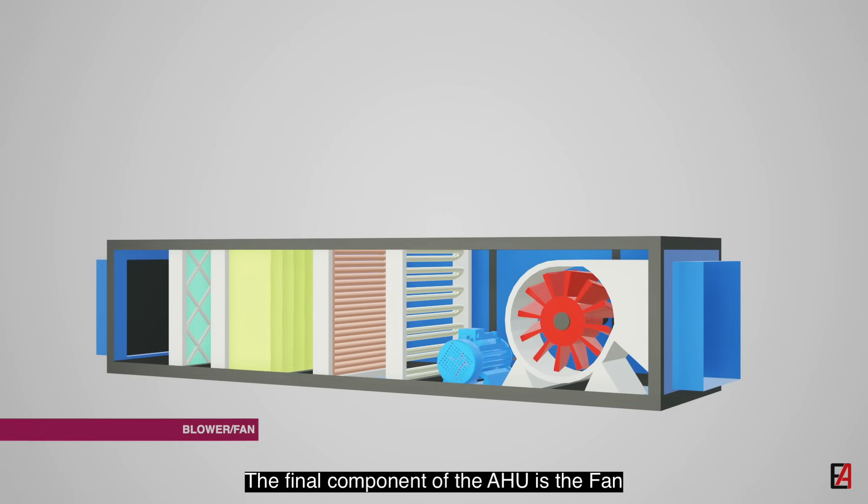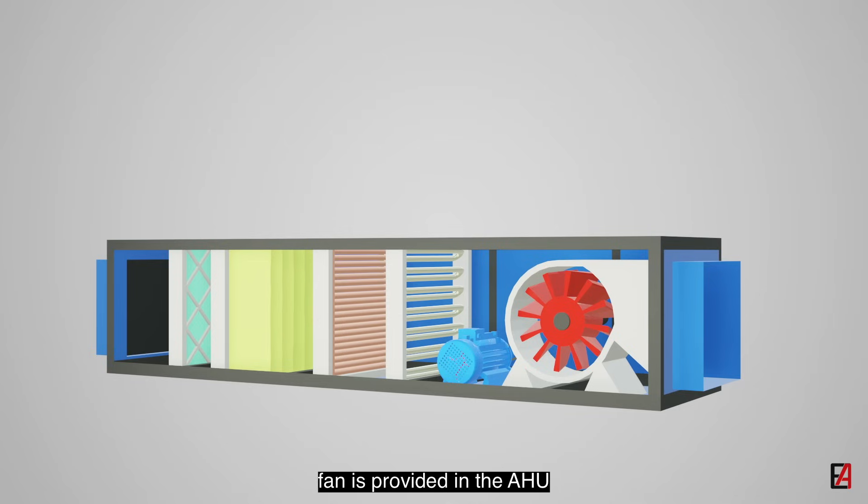The final component of the AHU is the fan. To push the outside air to the building spaces, the fan is provided in the AHU, which pushes the outside air into the building with the help of the ventilation system ductwork. These fans can be either single speed, dual speed, or can be equipped with variable frequency drives to control the speed of the fan. Fan is placed at the end of the AHU.